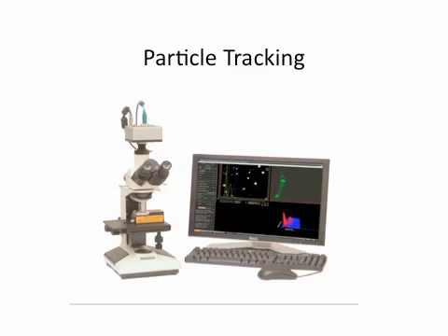Okay, so what's closely related to that? And that's particle tracking. This basically takes us all the way back to Jean-Baptiste Perrin, because that's what he did. He used a normal optical microscope to look at large particles, and he monitored the movement and correlated that back to the Einstein-Langevin/Smoluchowski theory. So the only difference with this particular equipment is that you can analyze particles that are smaller than you could see with a normal light microscope. And the little trick is that they don't look at the particle itself, they look at the scattered light of the particle. So you use dark field microscopy.